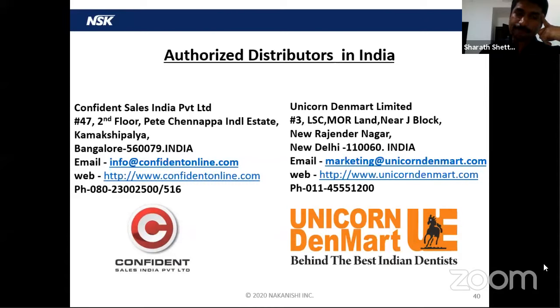These are the reasons. Last question from Dr. Indrajit. Red ring handpieces produce less aerosols. Does it mean it uses less water? No, of course not, because the water comes directly from the dental unit. The same water flow which comes to your regular aerator handpiece also. So the water flow will remain the same, but the only thing is less aerosol. The reason behind that is the involvement of air is comparatively less in a red ring handpiece as compared to your aerator handpiece. That's the reason.